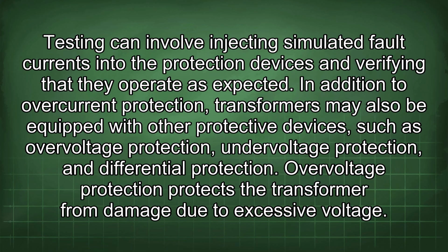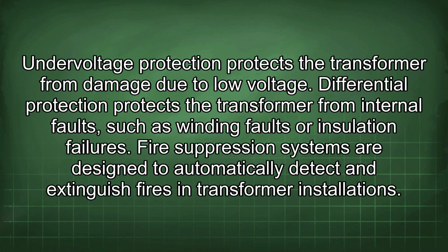In addition to overcurrent protection, transformers may also be equipped with other protective devices such as overvoltage protection, undervoltage protection, and differential protection. Overvoltage protection protects the transformer from damage due to excessive voltage. Undervoltage protection protects the transformer from damage due to low voltage. Differential protection protects the transformer from internal faults, such as winding faults or insulation failures.